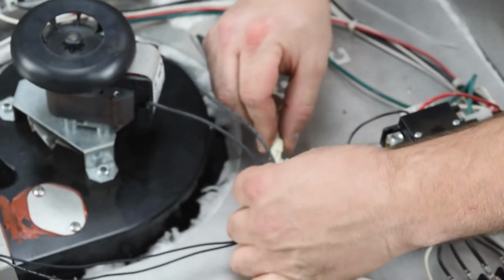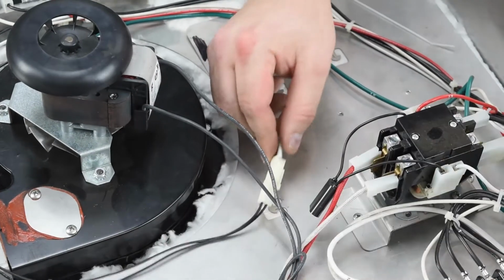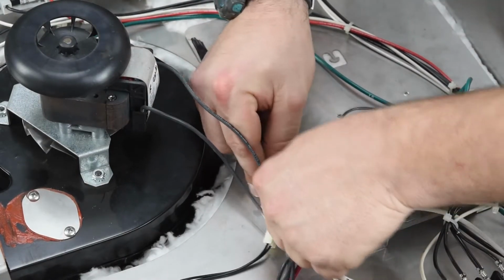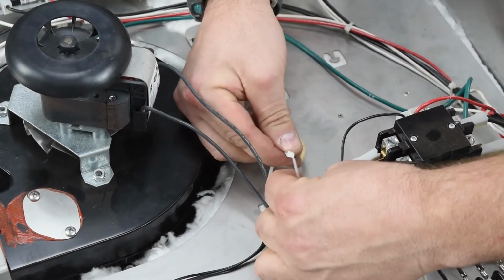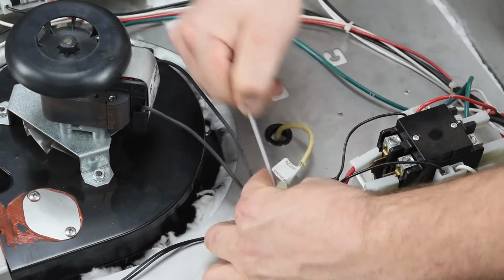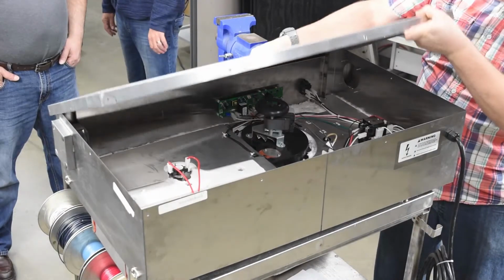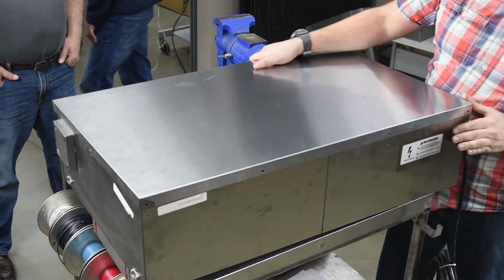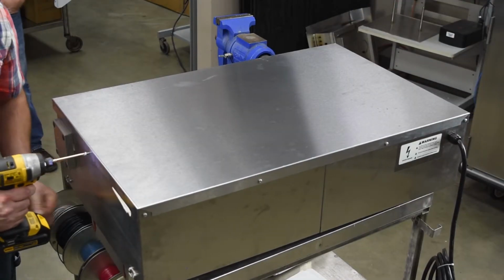Attach the new probe to the unit's provided wire. Secure the plug with a zip tie around the bottom of the unit where there is a tab shown. Finally, replace the top paneling of the unit, reinstall the 6 screws, and test the unit for normal operation.